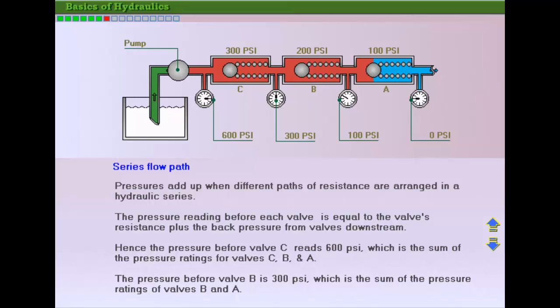Hence the pressure required to open valve C is 600 psi, which is the sum of the resistances for valves C, B, and A. The pressure reading in the gauge placed after valve A is theoretically zero, as there is no resistance downstream.